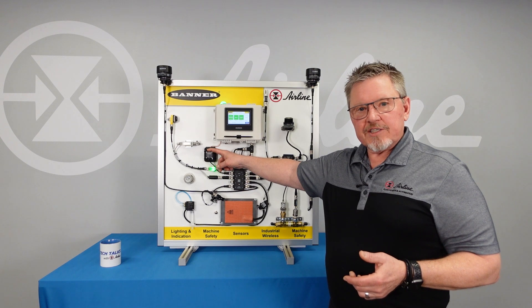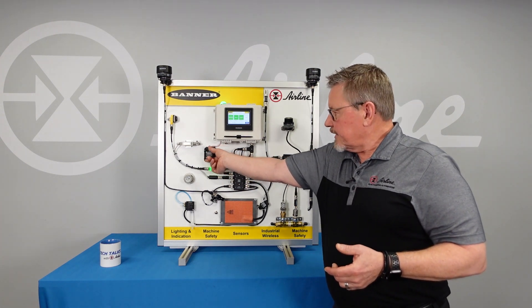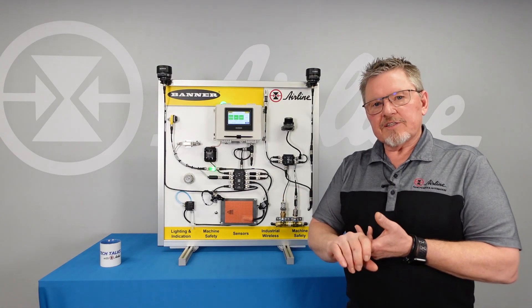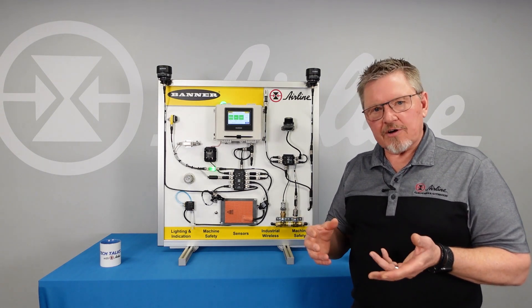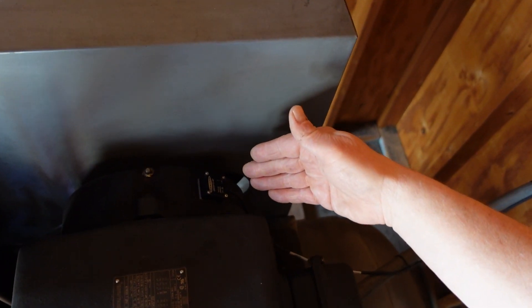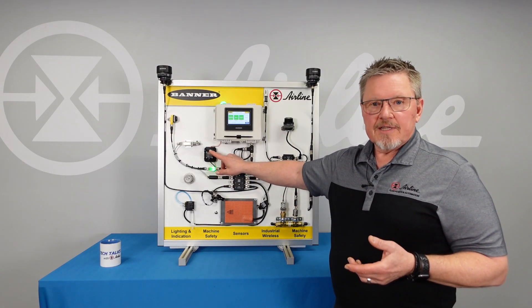On the left side I have a temp and vibration sensor. Put on a motor, it's held on magnetically and sits right on your motor. When your motor runs into a very high vibration — maybe a bearing is starting to go — or if something is going on with the motor and it's getting very hot, you can get an indication prior to the motor being damaged.